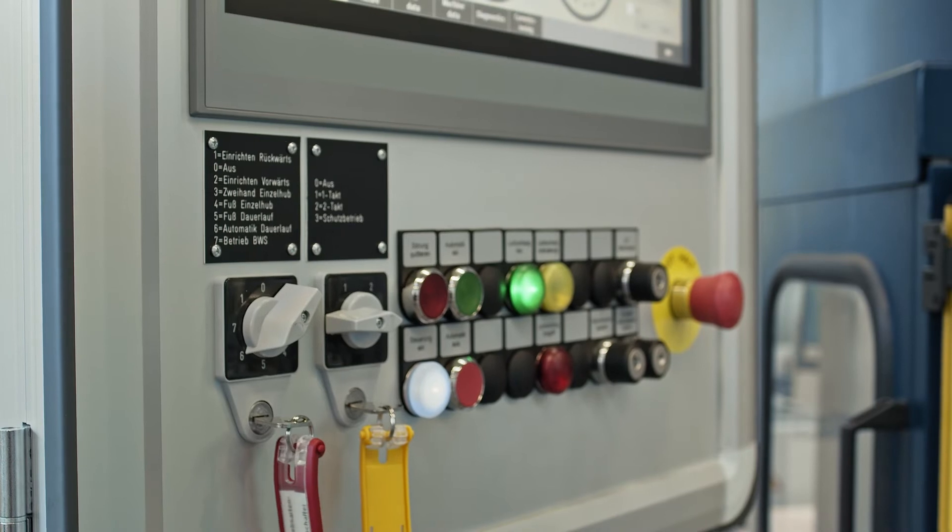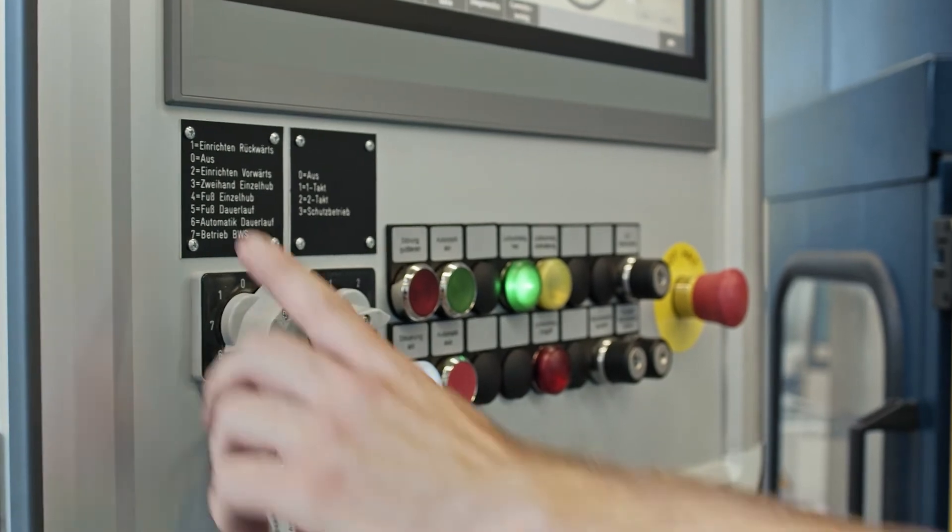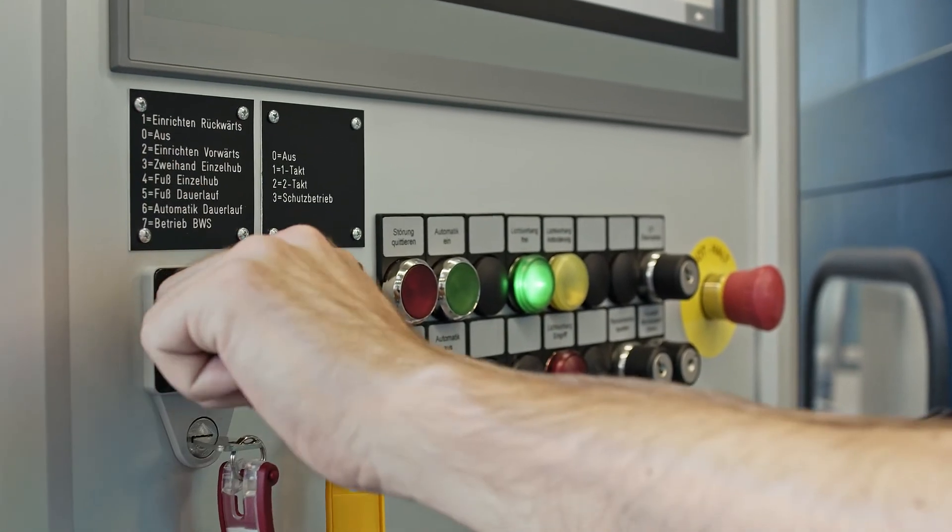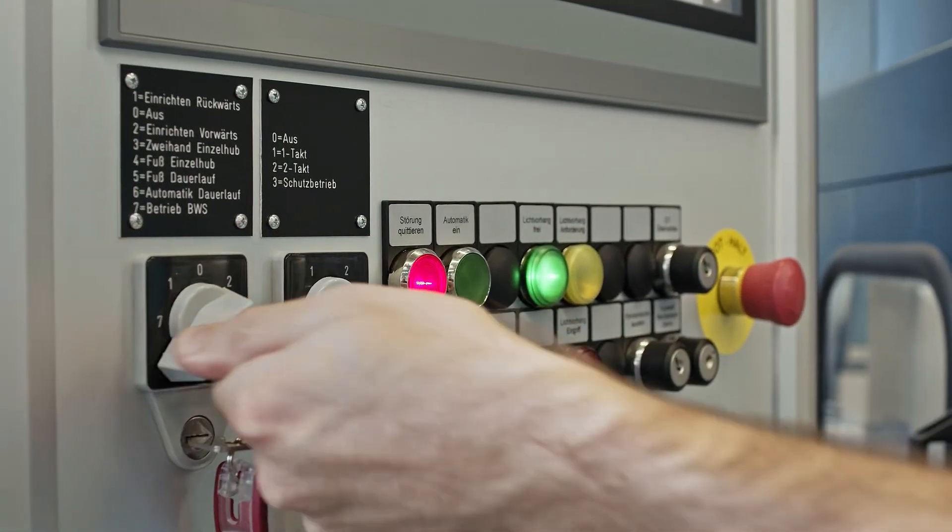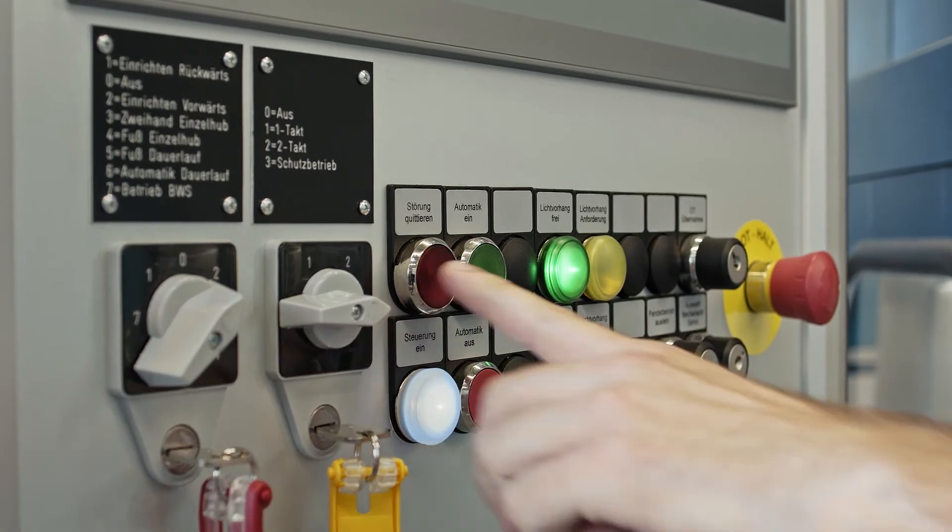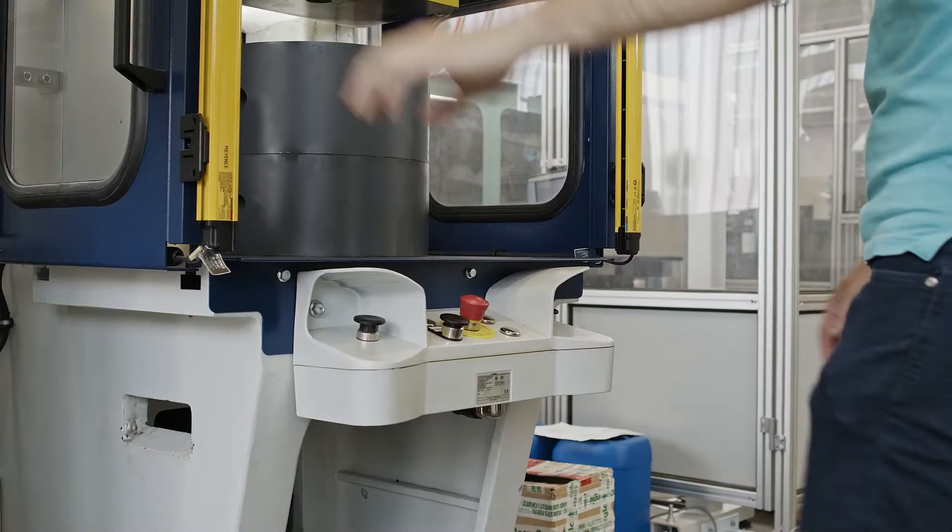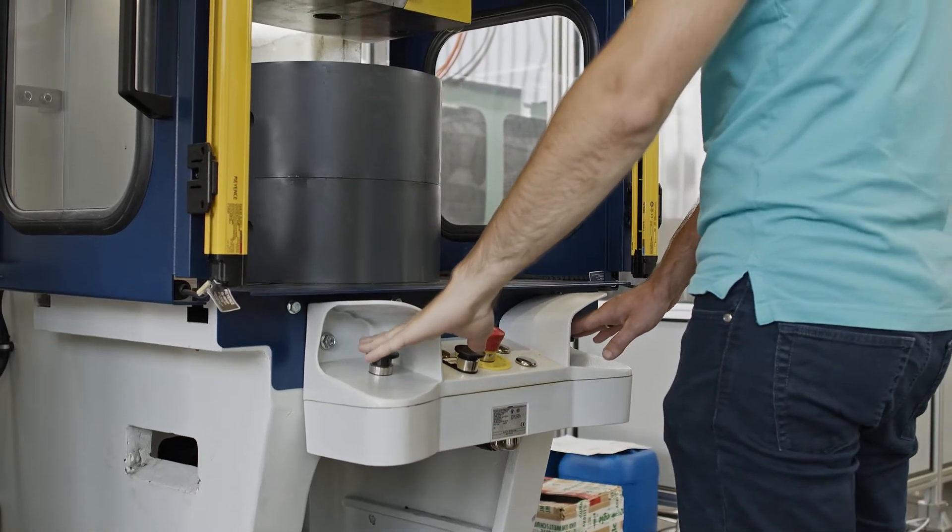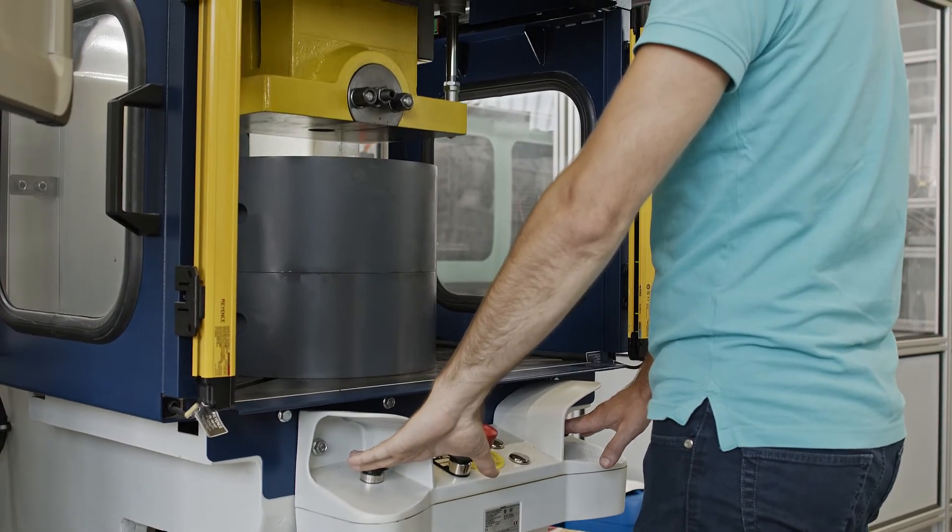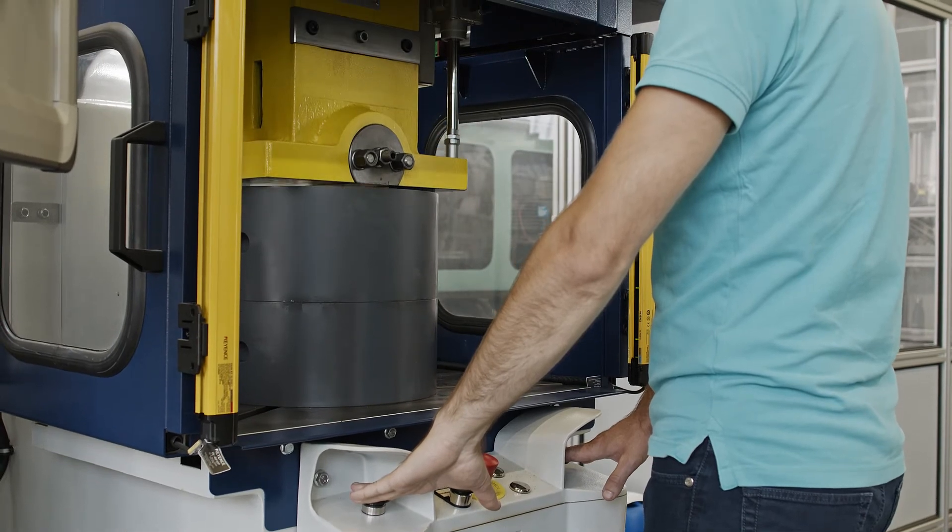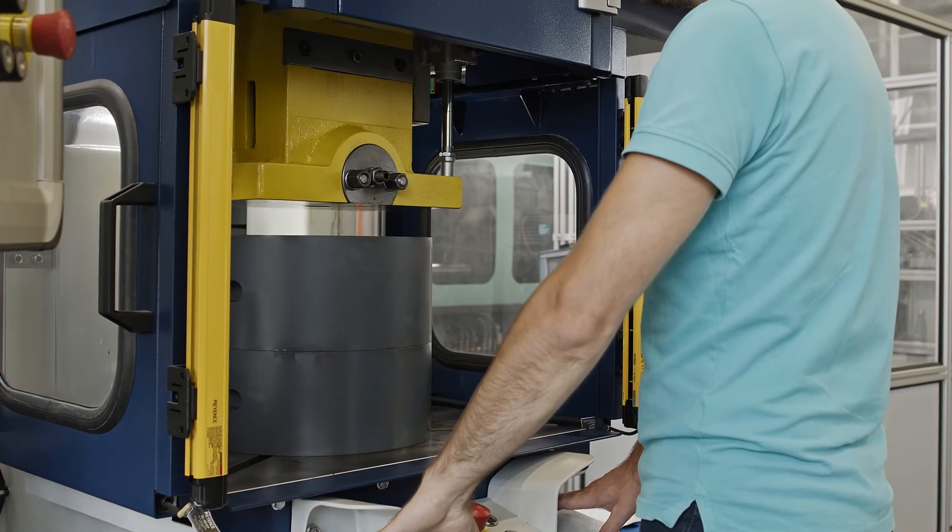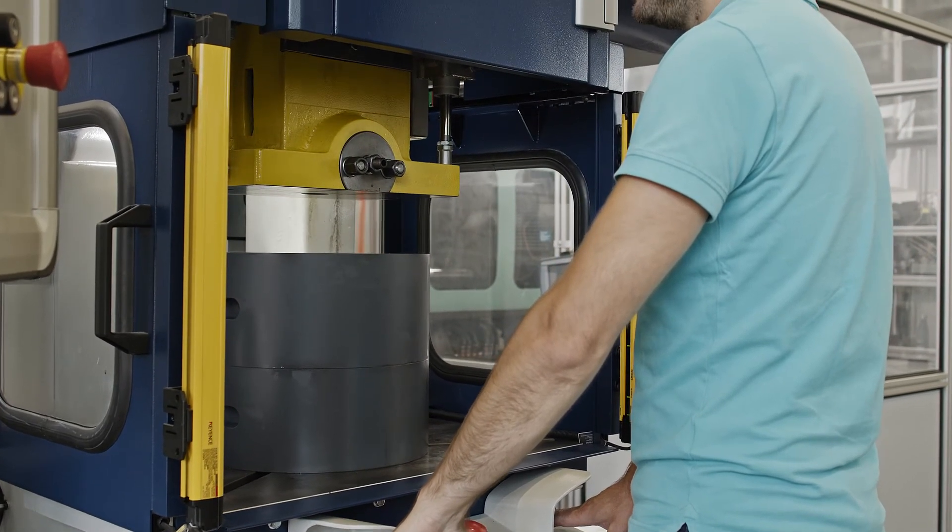In the next step, we show you the function of the two-handed operation in the setup mode. To do this, we first select the setup mode using the rotary switch, acknowledge the faults and proceed to two-handed operation. We see that the press ram is moving and in precisely this operating mode a safe speed monitoring of 20 strokes per minute is required. If this limit is exceeded, SS1 should be triggered as a stop response.